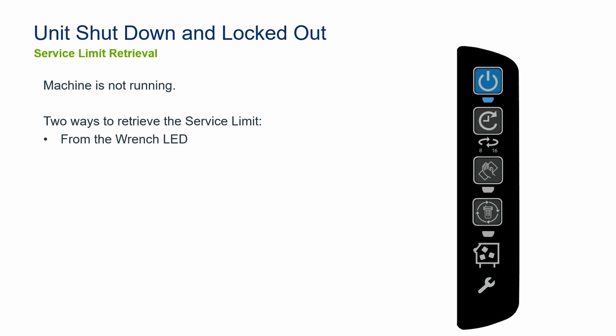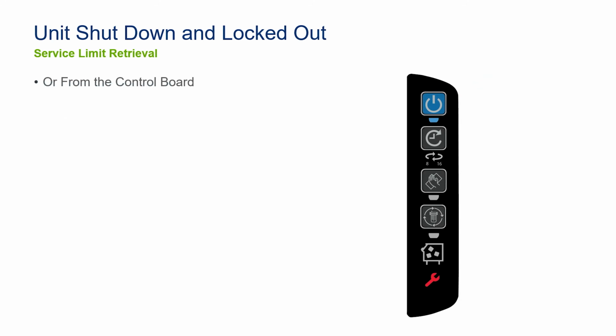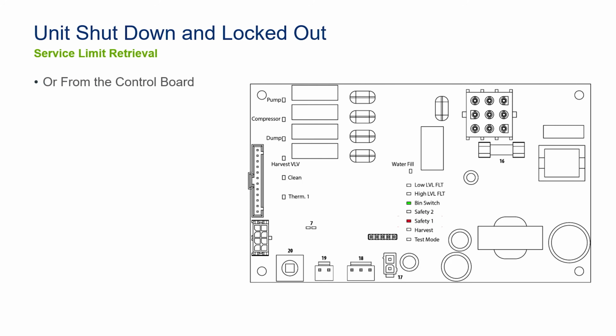So how do we figure this out from the board? You can go to the control board. The machine is locked out. You don't have to touch anything on this touchpad. Just look at that board. It's sitting there, not running, probably no ice in the bin. What you'll see is the safety one. That's what it's called out on the silk screen on the control board. We're referring to it as a service limit, but I want you to see what you'll see. It would say safety 1 on the board with that light lit solid. If the unit was empty and the damper was in the up position, you'd also see that bin switch light green, but we're really worried about the service limit here.